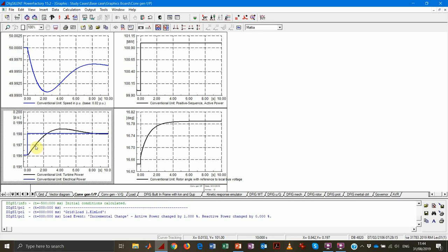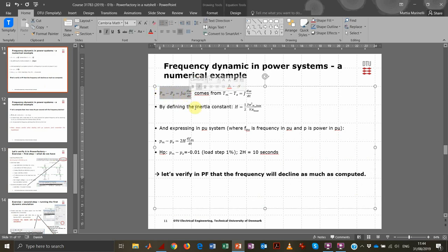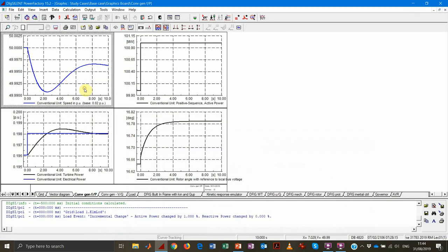The electrical power increases instantly, but the mechanical power follows with a delay, because we can't increase the amount of steam flowing in the turbine instantly — that takes a few hundred milliseconds or a few seconds depending on prime mover dynamics. This unit is extremely fast due to its fast valving capability, but it still takes a while. This difference between mechanical power and electrical power — the imbalance between the two torques — translates into a dynamic of the generator's rotational speed, and hence into a dynamic of the electrical frequency.